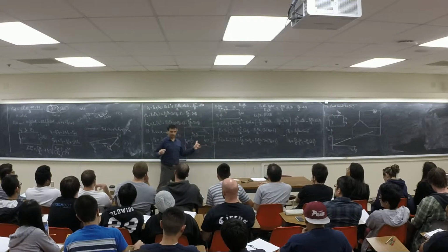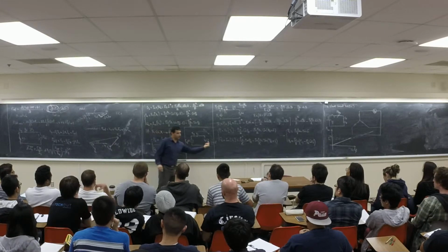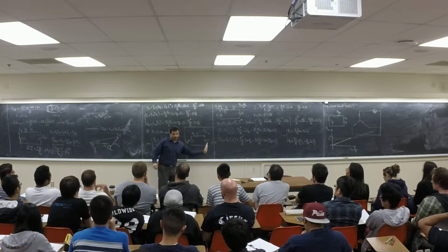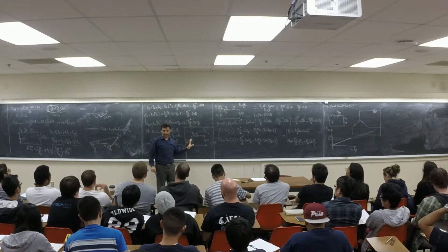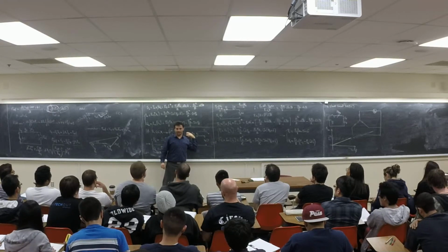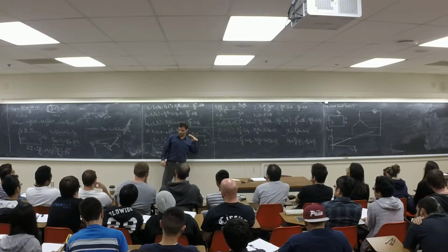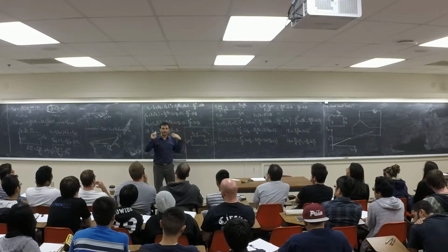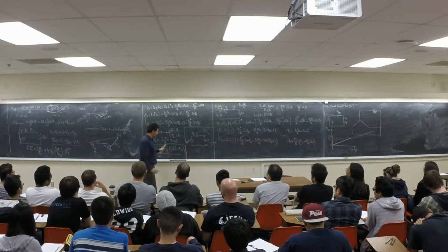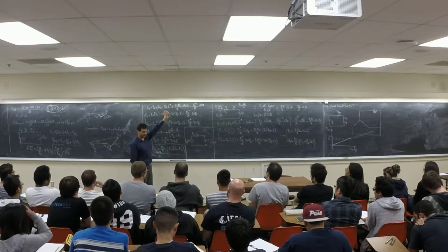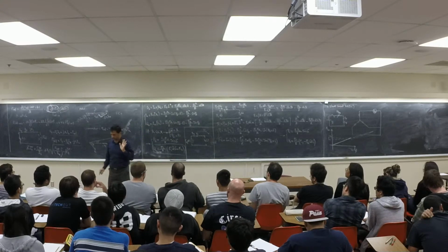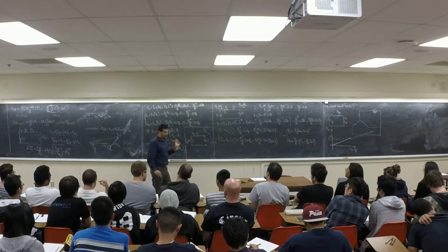Or vice versa. If this one is negative, the reactive power is coming this way. So if you look at here, reactive power is going this way, meaning this generator is acting like a capacitor, because it's generating reactive power. But if Q2 is negative, it's absorbing the reactive power. It's like an inductor. An induction machine can only use Q, it cannot generate Q. But a synchronous machine can go either way. Some synchronous machines are designed to have P equal to 0, but they can change Q to be either positive or negative. They call it a synchronous condenser machine.